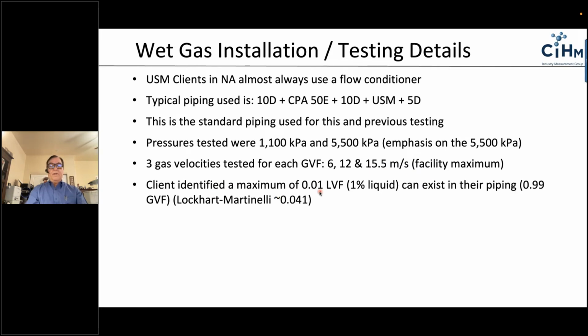Clients identified the maximum liquid loading at about 1%. In the multi-phase world, people like to talk about liquid volume fraction and gas volume fraction. So a liquid volume fraction of 0.01 is equal to 1%, or the same would be 0.99 for gas volume fraction. For those multi-phase folks in the wet gas world, this works out to be a Lockhart-Martinelli, which is kind of like the Reynolds number, if you will, of the wet gas world, of 0.041.